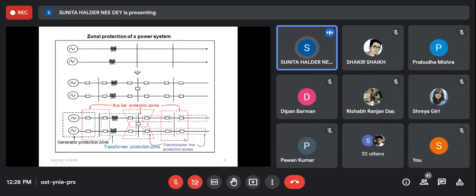Now, how is the protection incorporated? So you have seen this type of single line diagram for the power system. That means a generator, a transformer, then a transmission line. Here there is a double circuit line with two generators, so they are shorted, and these are bus bars. Now, when we apply the protection, if we want to protect this zone, then we subdivide this zone into some subzones. Say here we incorporate one subzone.